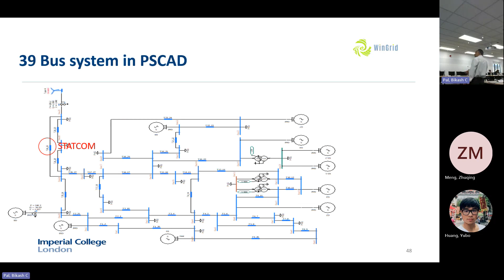So what we did, we have 1, 2, 3 zones. How we got these zones is the MVA level, the fault level. Here you could see the fault level is very, very low, which means this part of the network is very weak. This part of the network is very strong. Maybe there are a large number of synchronous machines here.